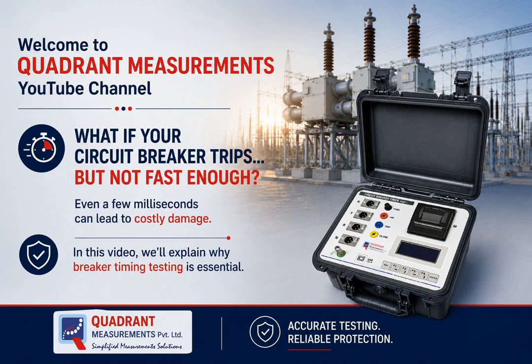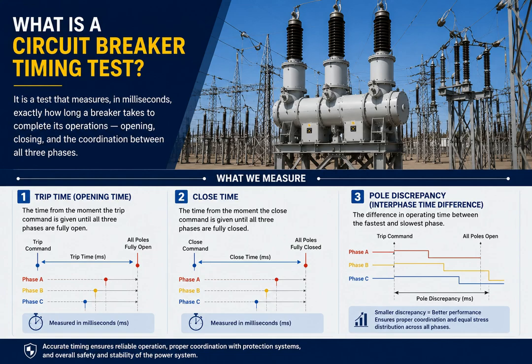So what exactly is a circuit breaker timing test? It is a test that measures, in milliseconds, exactly how long a breaker takes to complete its operations. That is opening, closing, and the coordination between all three phases. Specifically, we measure trip time, close time, and pole discrepancy, that is the difference in timing between phases.